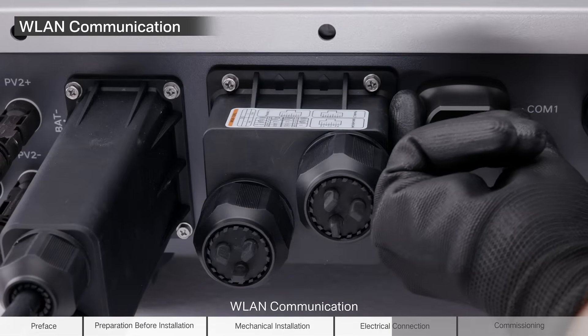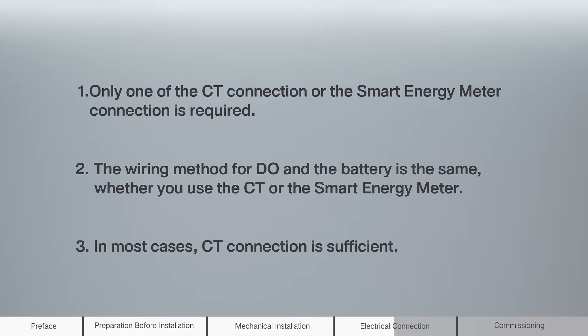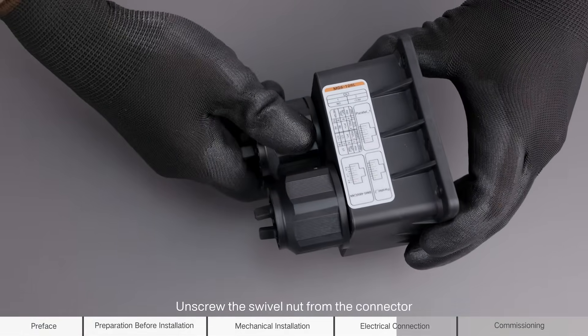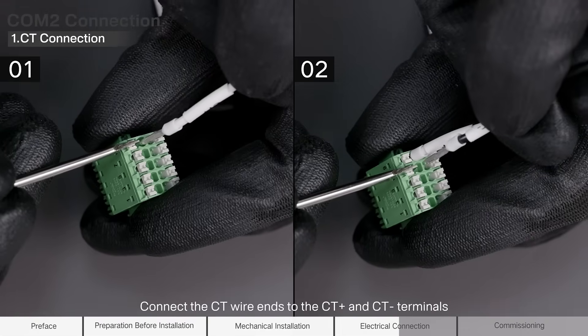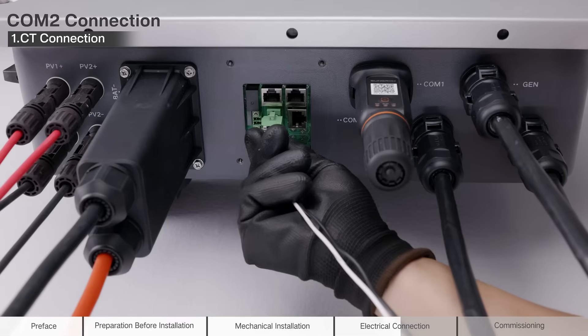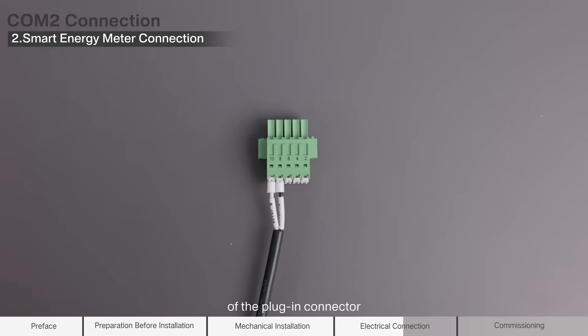WLAN communication: remove the waterproof lid from the terminal and install Ynet S2. COM2 terminal communication connection. Unscrew the swivel nut from the connector, then remove the terminal block. Remove the sealing ring. Route the crimped CT cables through it. Connect the CT wire ends to the CT Plus and CT minus terminals on the pluggable connector. Connect the wire head to the cord end terminal. The wire end is connected to the smart energy meter, and the other end is inserted into the meter port of the plug-in connector.